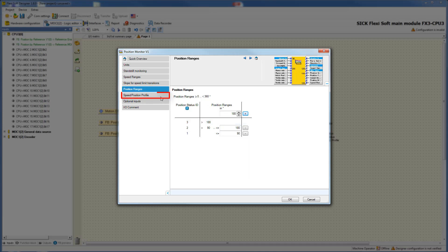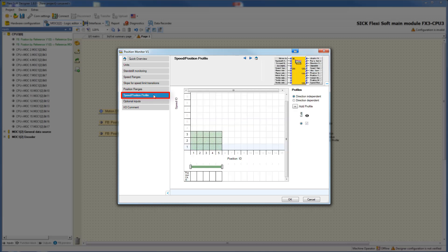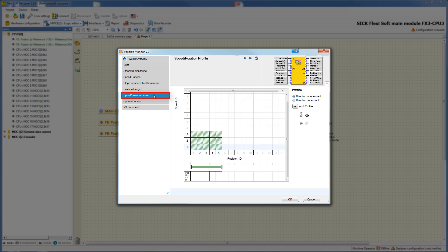In the next tab, speed position profile, you have the possibility to configure profiles. Depending on the current position, different speeds or directions can be allowed. In the matrix you can see on the horizontal the previously defined position ranges and on the vertical the defined speed ranges. You can select the maximum permissible speed range for each position range. The permissible speed ranges are shown in green, and by clicking on the desired fields you can configure the speed position profiles.